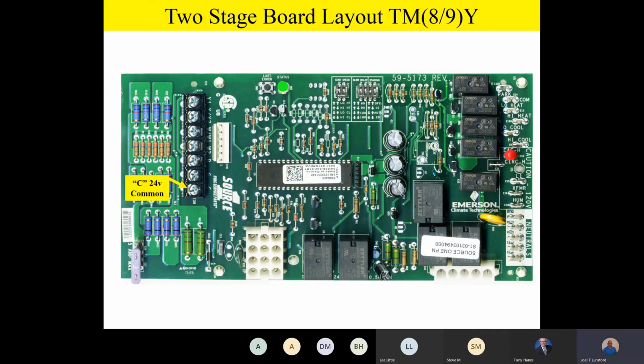Okay, team, as we move around the board, just like we had before, towards the top of the board, we have a last error button. We can retrieve errors, and again, just like before, the last 5 errors are remembered. If you hold that button down about 10 to 15 seconds, you'll reset the memory. We have a tricolor LED, just like we had before. It'll flash either red, green, or yellow based on the flash code that you're looking at.